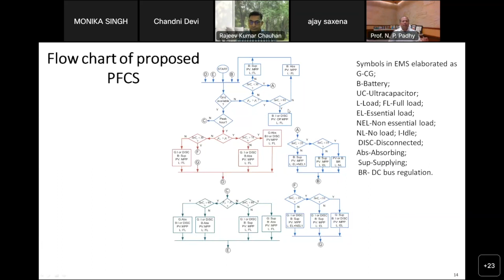This is the control scheme already available, and this is the standard flow chart I explained orally: for example, if the SOC is less than 30%, don't discharge; if SOC is more than 30%, it can discharge, and so on. If SOC is more than 90%, do not charge; if SOC is less than 90%, it can charge, and so on.